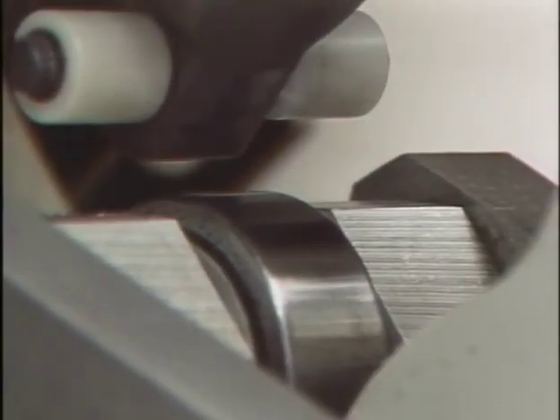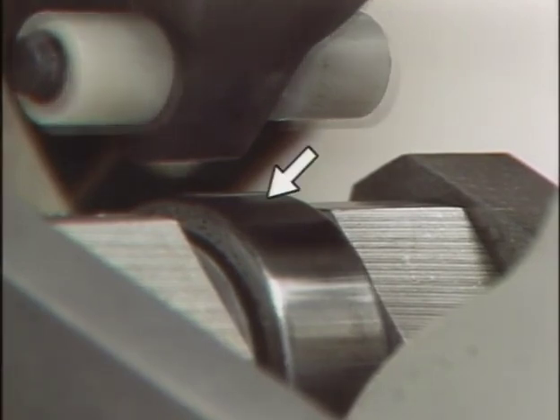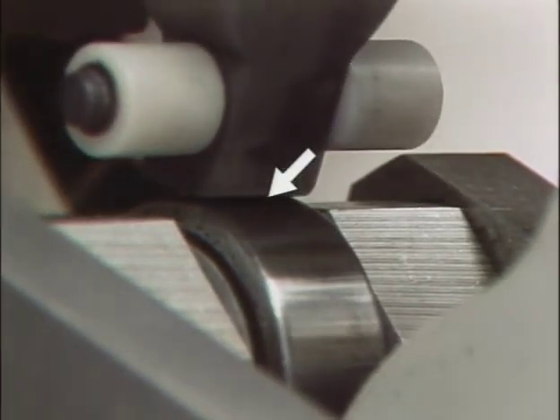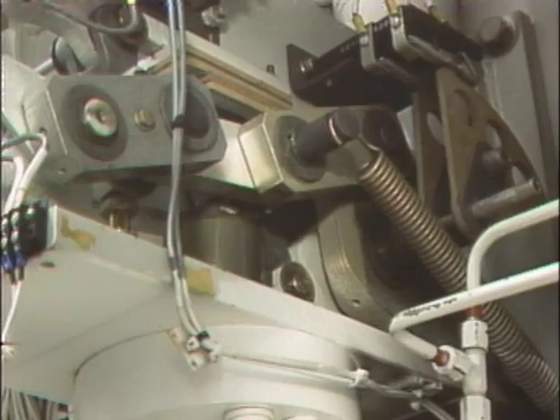Latch wipe is checked. Latch wipe is a measurement of how much of the surface of a latch rests against a roller or other component to hold the operating mechanism in a given position. Latch clearance is also checked. Latch clearance is the amount of clearance needed for a latch to consistently drop into a given position.